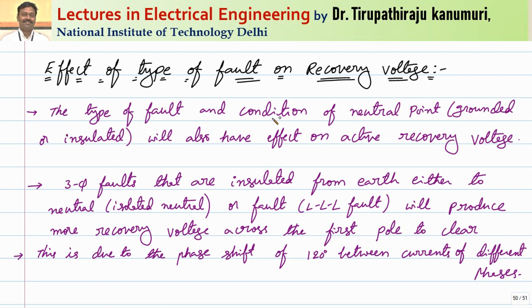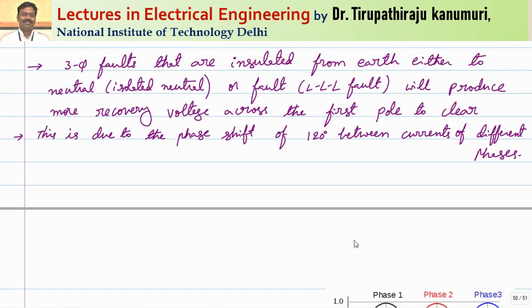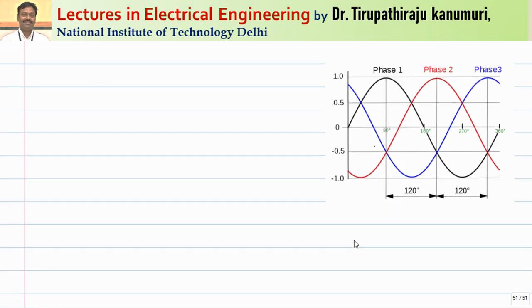The type of the fault and the condition of the neutral point — whether the neutral is grounded or insulated, or whether the fault is a grounded or ungrounded fault — will have an effect on the active recovery voltage. For three-phase faults that are insulated from the earth (isolated neutral case) or a triple-L fault not associated with the ground, more recovery voltage will be produced across the first pole to clear. This is due to the phase shift of 120 degrees between currents of different phases, and many of you questioned how this comes about, so I want to clarify it in detail.